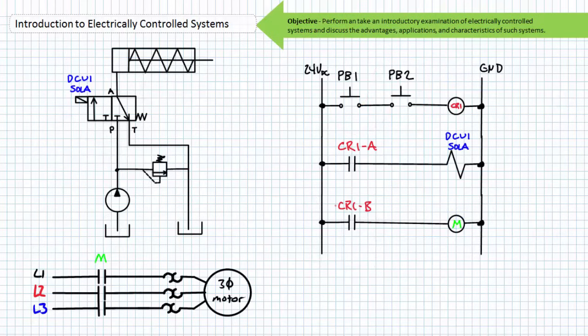Consider additional functionality offered to this electrically controlled system by slightly increased complexity internal to the ladder logic diagram. These extra rungs act almost like parallel paths if one was to draw this circuit using traditional schematics. Consider a control relay CR1 and its associated contacts, normally open CR1A and normally open CR1B. In its de-energized state, these associated contacts would not allow conduction from the high to low side of the ladder logic, and both solenoid A and the M coil of the contactor would be de-energized.